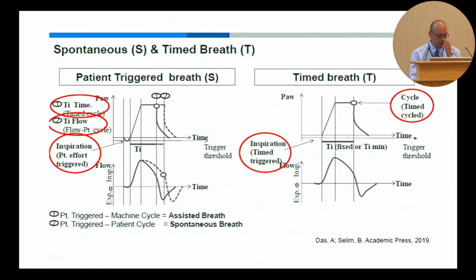Now these slides are a little complicated, so I'll try to make it a little simpler. And this is what is related typically to the different brands of AVAPS. The Respironics device, when you set it on AVAPS ST, ST means that there is a spontaneous breath and a timed breath. And Respironics treats each breath differently. So this graph here on the left has two breaths, and number one is triggered by time. So you see here time cycle. This is what is called the timed breath. So in Respironics it will be the T part. Number two is the one that is cycled by flow. This will be number two here that is a little later.